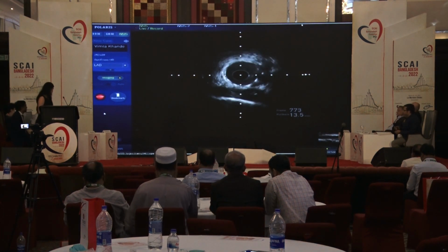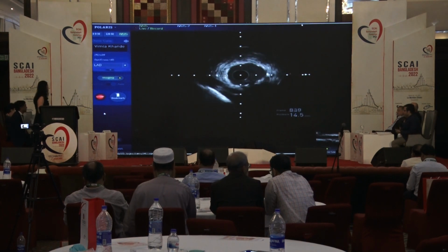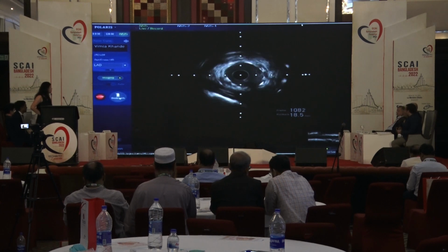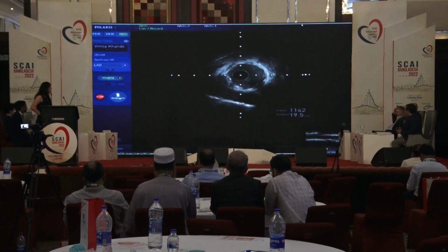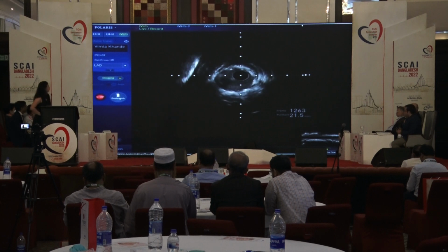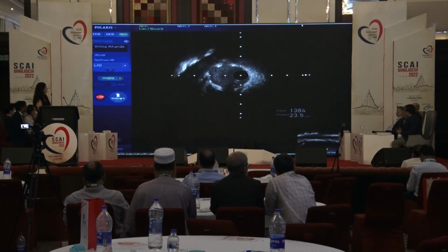The key is that once you have done two ablations and you cannot cross through, you can always crank up your speed. Clearly, ablation efficiency goes down at the lowest speed. You want to go to the highest speed.